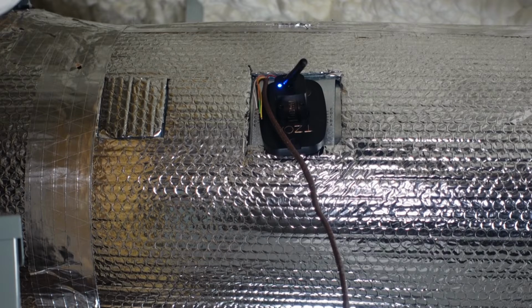Now is the time to activate the power to the monitor and the air handler, and we'll need airflow in the duct for the next step. The monitor's LED should be solid blue. If the LED isn't solid blue at this point, please refer to the monitor LED status video to learn how to reset it back to factory default states.